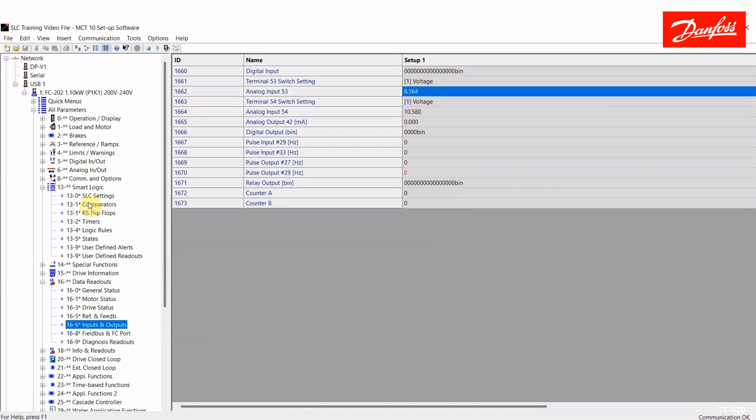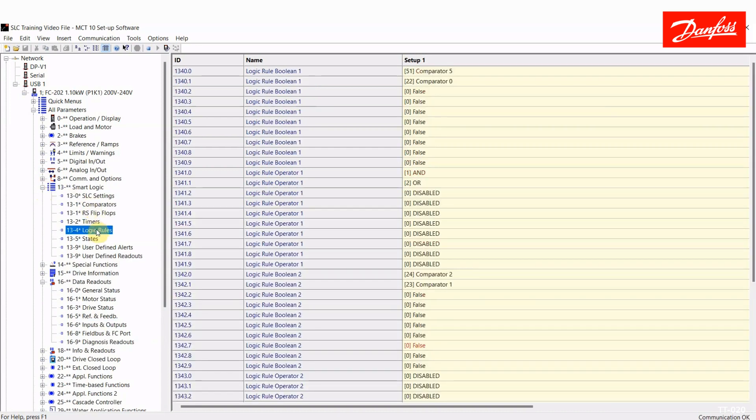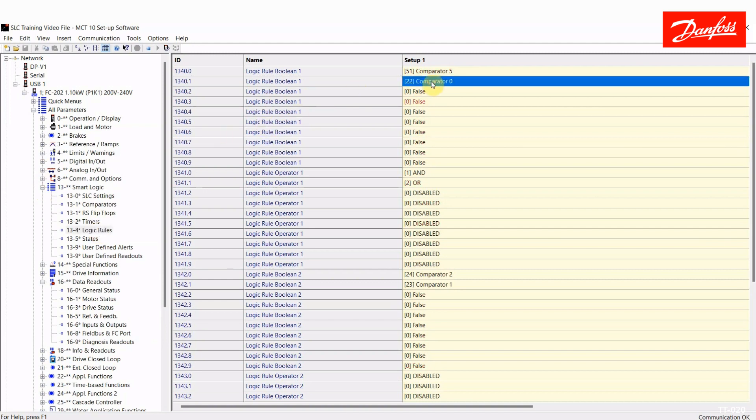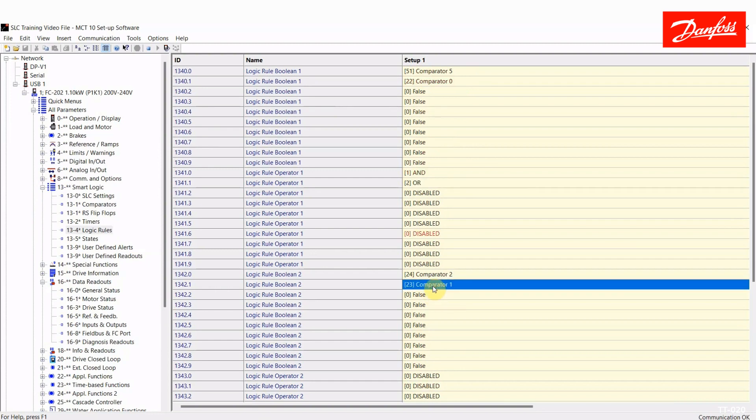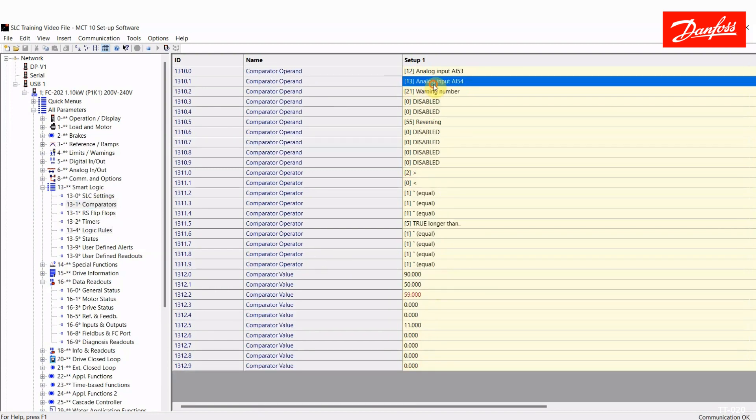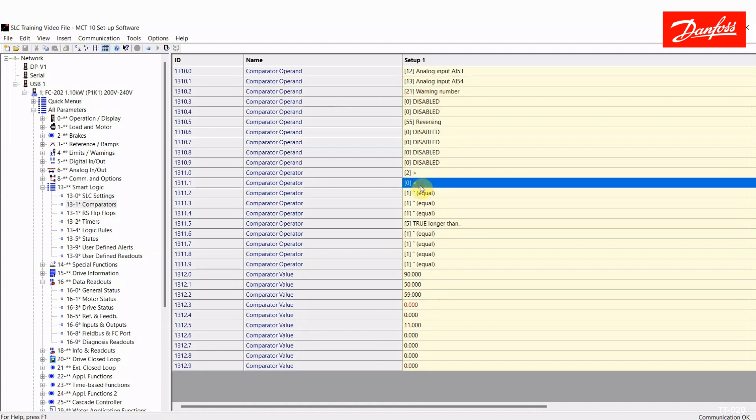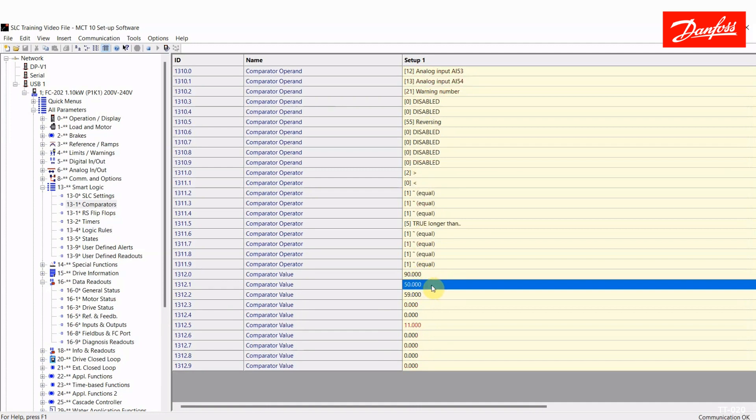Now I'm going to move on to a logic rule. So a logic rule can be more complex than just a single comparator. Here you can have multiple things tied in. So I have created a logic rule that says comparator 0 that I just demonstrated, saying analog input 53 is greater than 9 volts or comparator 1. Comparator 1 says that analog input 54 is less than 50% of 10 volts or 5 volts. So now I have a logic rule that's going to be true when either AI 53 is greater than 9 volts or analog input 54 is less than 5 volts.